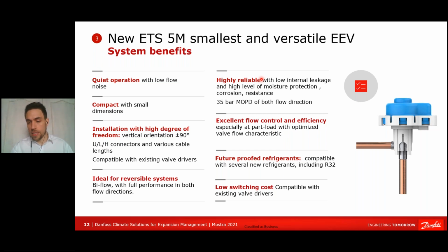As I said at the beginning, it's compatible with all the new refrigerants, meaning it moves from R134A, 454B, R32, propane, and even R744. It also comes suitable for all three applications. Normally those applications are for much bigger sizes, but you can use these valves for derivative circuits just for cooling your motor, for instance if you have a Turbocor compressor needing a cooling circuit just for the motor itself.